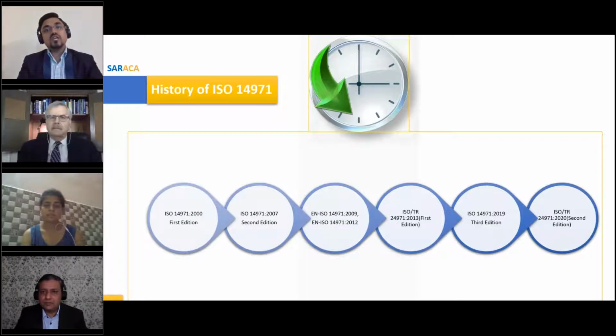First, 24971 was launched in 2013. That was the first edition of 24971. Then the ISO 14971 third edition, the 2019 version, came into effect in 2019. Then ISO 24971 was revised from the first edition to the second edition in 2020, and that was updated according to the ISO 14971 2019 version. So you can refer to 24971:2020 to follow the process of how you can implement the risk control measures which were defined in the third edition of 14971.